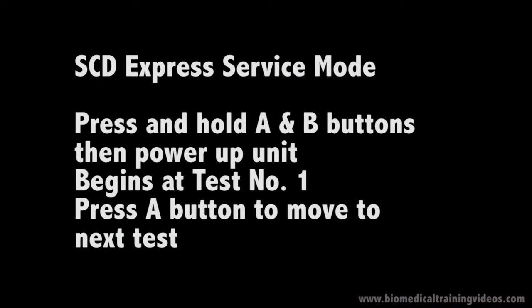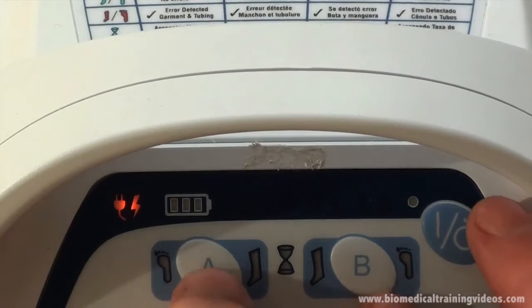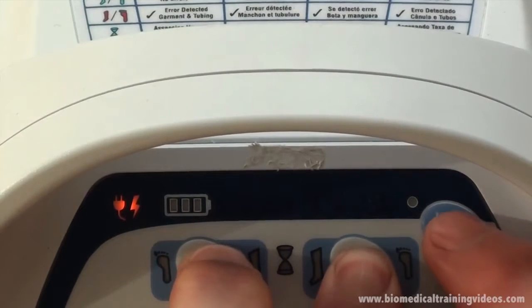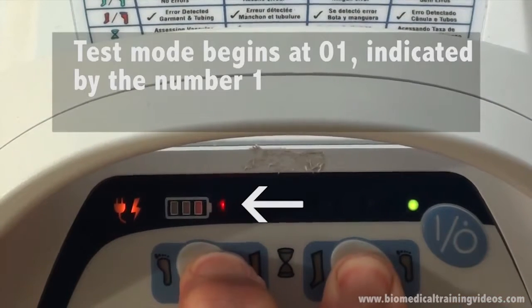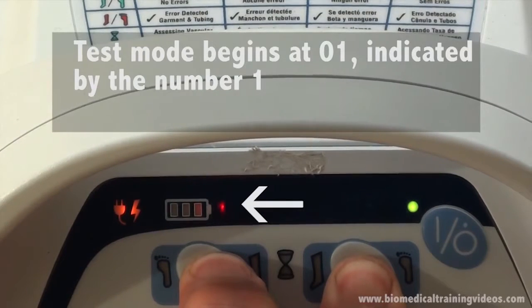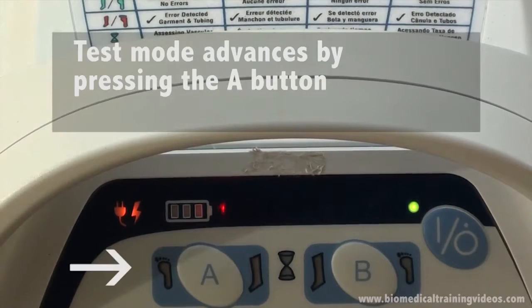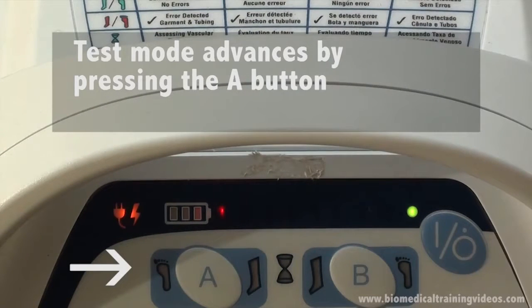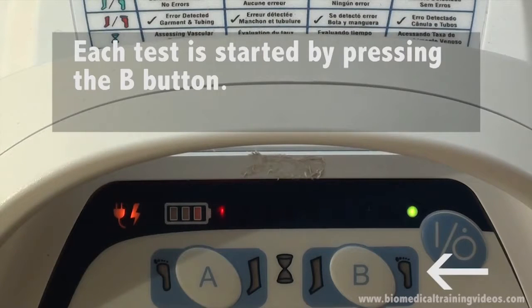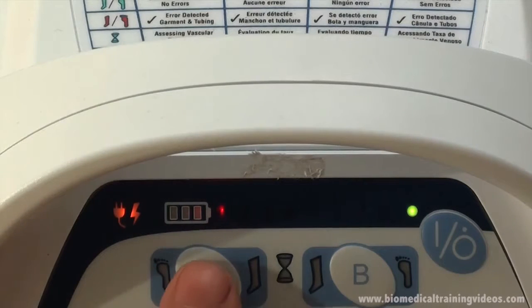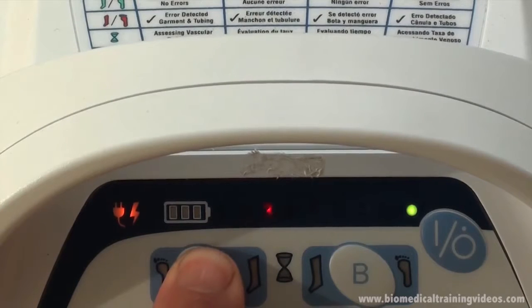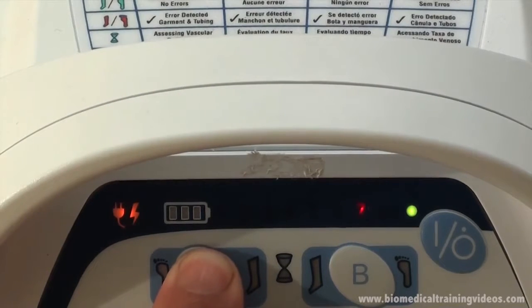Now we'll go through the service mode. This is activated by holding A and B buttons down when powering up the unit. And we begin at test number 1. So the number 1 indicates test 01. And we advance through the test by pressing the A button. And then we start each test by pressing the B button. Just showing it advancing through 1, 2, 3, 4, 5, 6, 7, 8, and back to the start again.